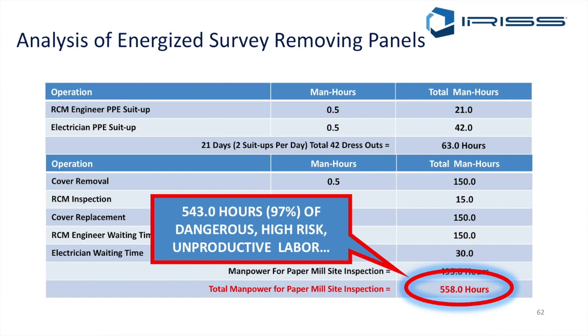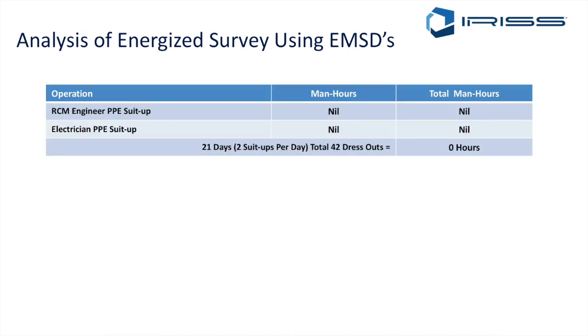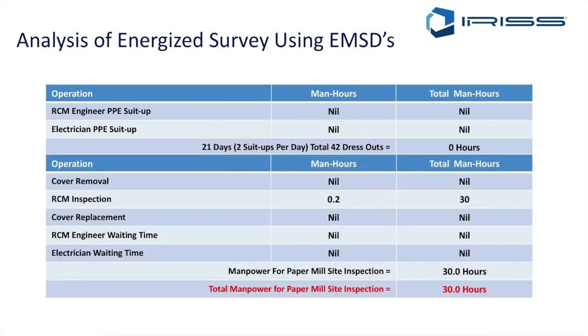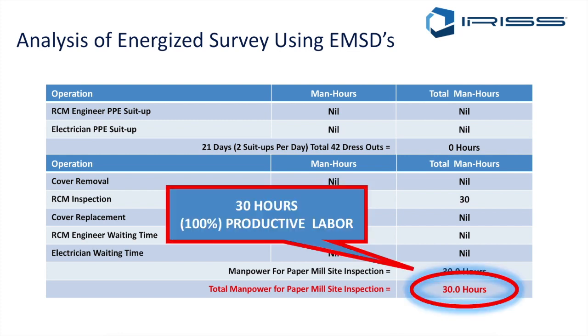Now with the infrared windows installed, there's basically no PPE suit up time, because the panel is in an enclosed and guarded condition, so we can get all of our data from the panel in a closed and guarded condition. So there's no cover removal. The RCM inspection we gave 30 hours to complete. Cover replacement: zero. So the complete inspection, including report generation, is 30 hours - and that's 30 hours of safe, productive labour.